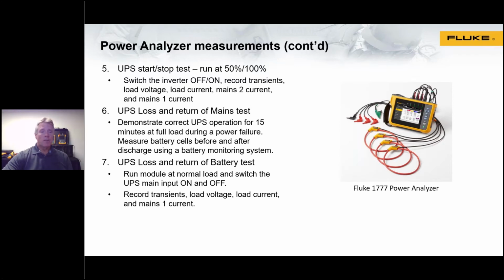Next test is a UPS loss and return of mains test. So what you want to do is, again using your load bank, demonstrate correct operation when operating at full load off the UPS to simulate a 15-minute power failure. There you would use a separate type of tool, or maybe a battery monitoring system, to look at the battery cells before and after that 15 minutes of runtime.